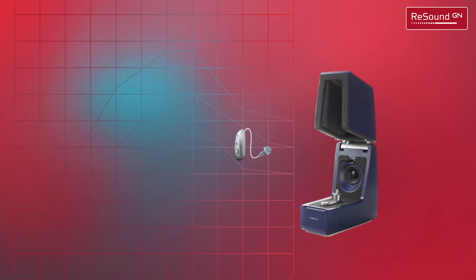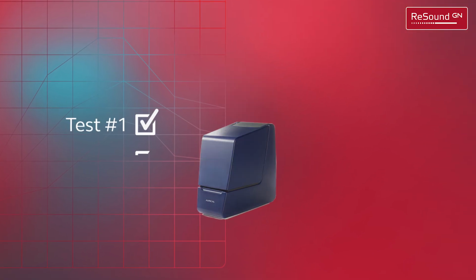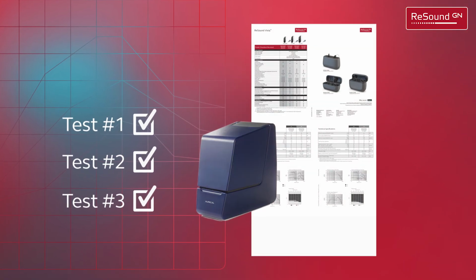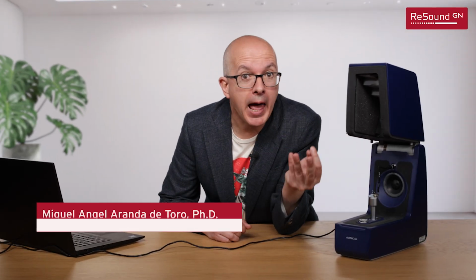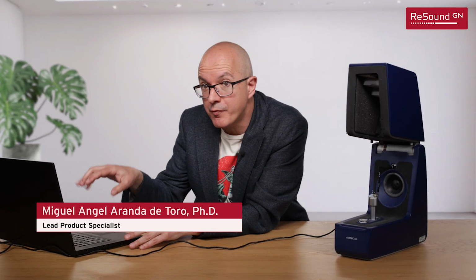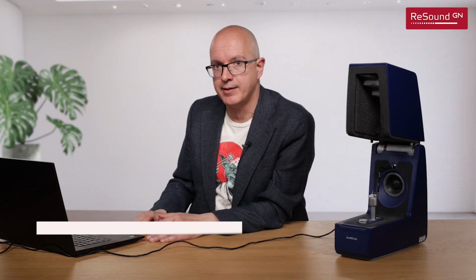What do you do when you don't know if your hearing aids are working properly? Well, if you have a test box like this, you can easily run a series of standardized tests to see if the hearing aid is healthy and working according to the specifications from the manufacturer. But guess what? Until now, running these measurements in the fitting software was not easy.